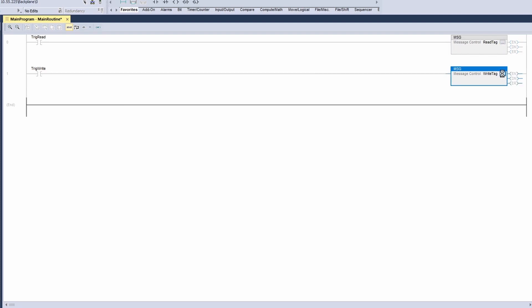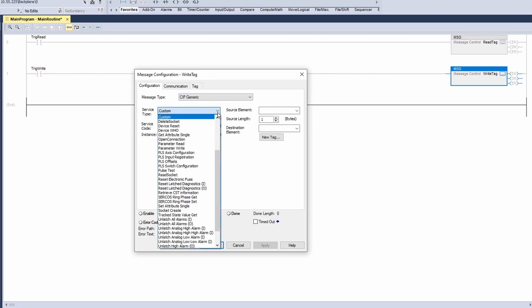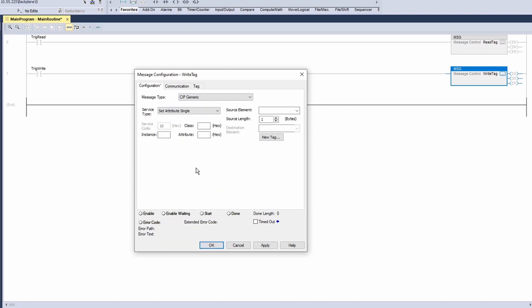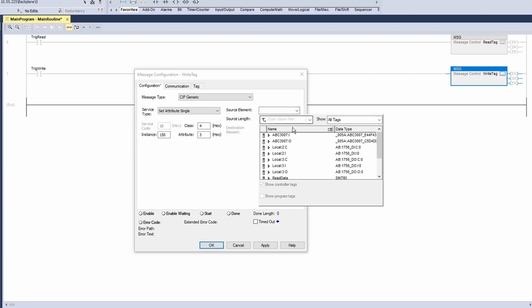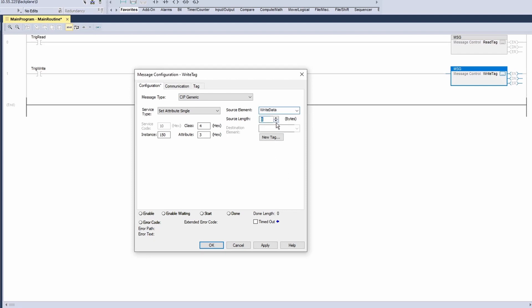Open the configuration dialog for the write tag message instruction. Set the service type to set attribute single. Enter class 4, instance 150, attribute 3. Click new tag and name it write data. Set the data type to an array of 1. Click create. Select the created write data in the source element. Change the source length to 0 as we are not writing any data.